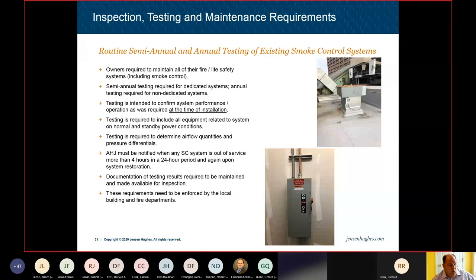That testing is required to determine airflow quantities and pressure differentials. So that certified air balance person needs to come through and take all those various measurements. The AHJ also, like other life safety systems, needs to be notified when any smoke control system is out of service for more than 4 hours in a 24-hour period, and again, upon system restoration. So there are some notices that go along with a lot of the other fire and life safety systems. You have to document the test results, which are required to be maintained and made available for inspection. That semi-annual or annual test report for the smoke control system needs to be provided to the property manager or to the owner so they can hold on to it.